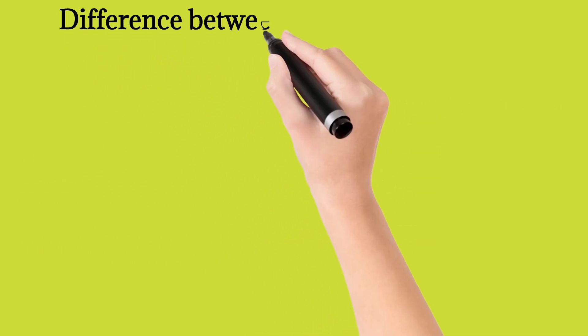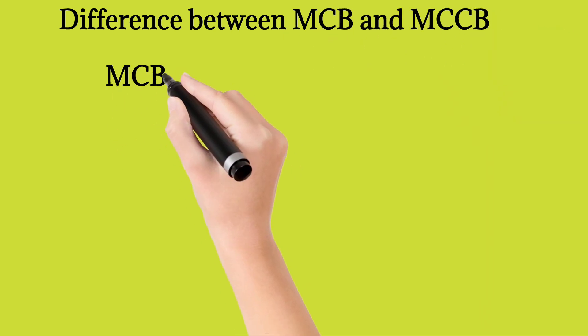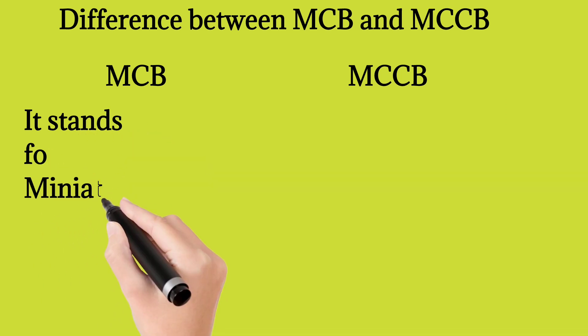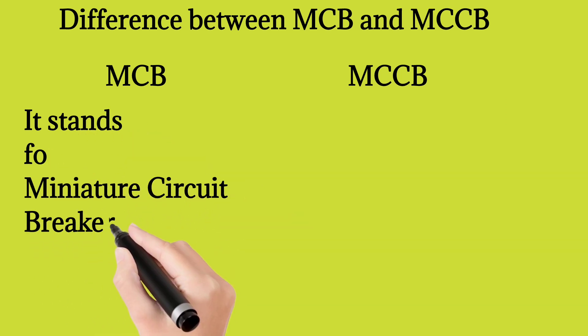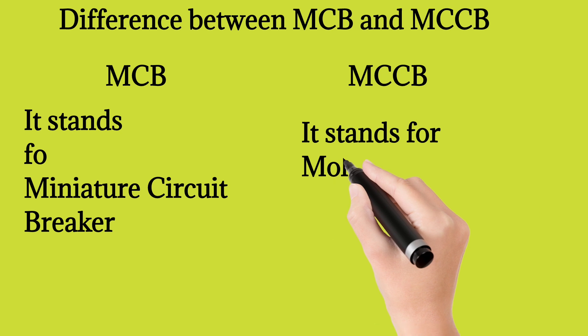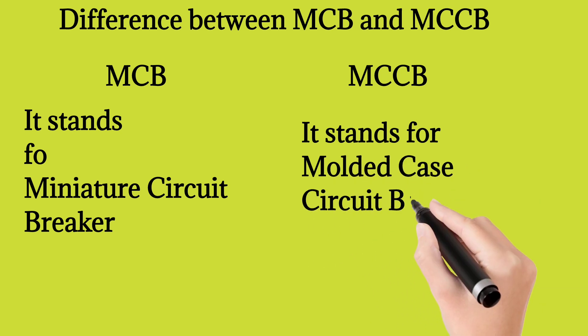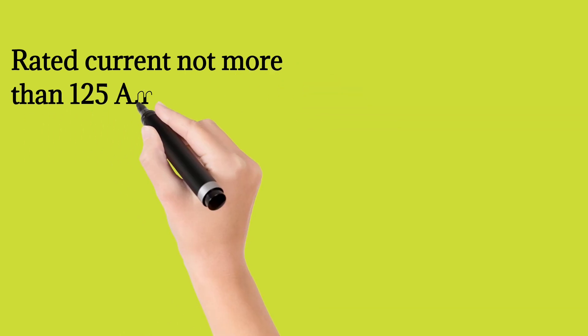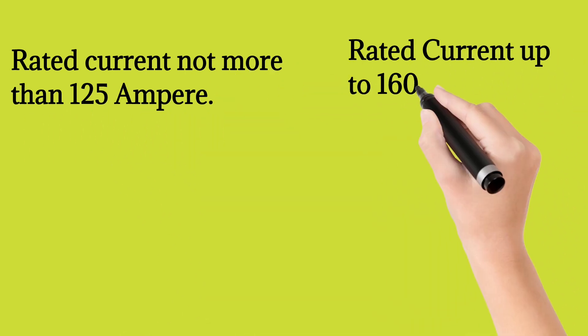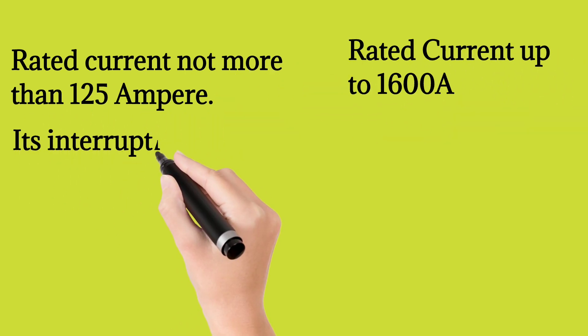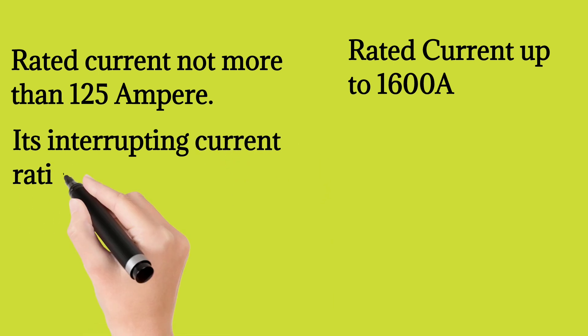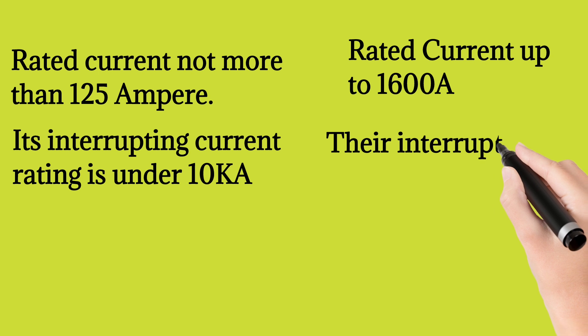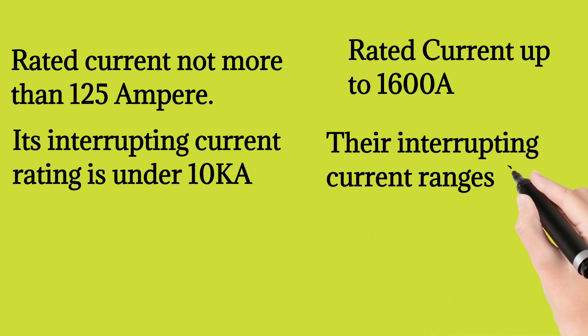Difference between MCB and MCCB: MCB stands for Miniature Circuit Breaker; MCCB stands for Molded Case Circuit Breaker. MCB has a rated current of not more than 125A, while MCCB has a rated current of up to 1600A. MCB's interrupting current rating is under 10kA, whereas MCCB's interrupting current ranges from around 10kA to 85kA.